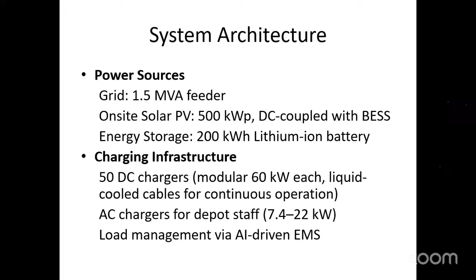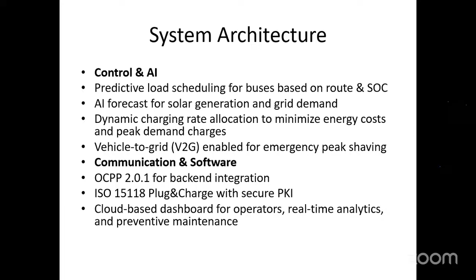Charging infrastructure consists of 50 DC chargers, modular 60 kilowatt each, liquid-cooled cables for continuous operation, AC chargers for depot staff, and load management via AI-driven EMS. Then in control and AI: predictive load scheduling for buses based on route and SOC, AI forecast for solar generation and grid demand, dynamic charging rate allocation to minimize energy cost and peak demand charges, vehicle to grid enabled for emergency peak shaving. Then in communication and software, they are using OCPP 2.0.1 for backend integration, ISO 15118 plug and charge with secure PKI, a cloud-based dashboard for operators, real-time analytics, and preventive maintenance.